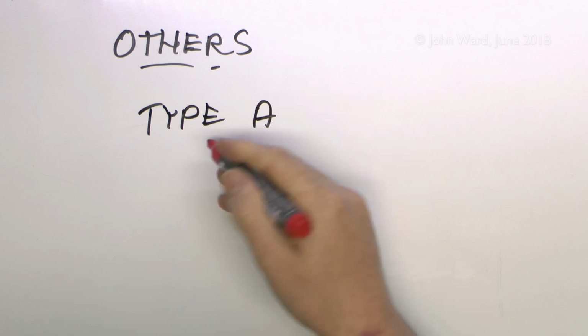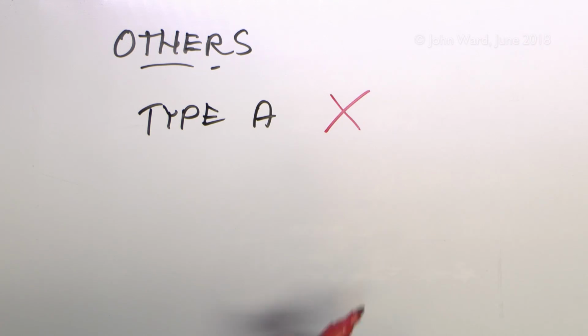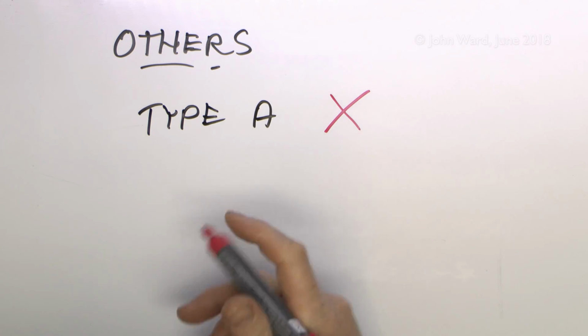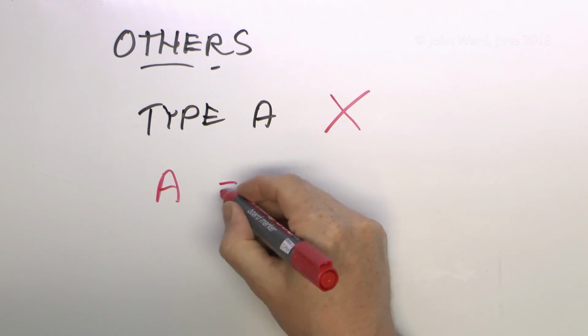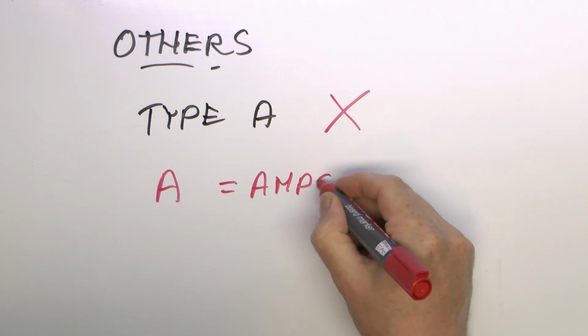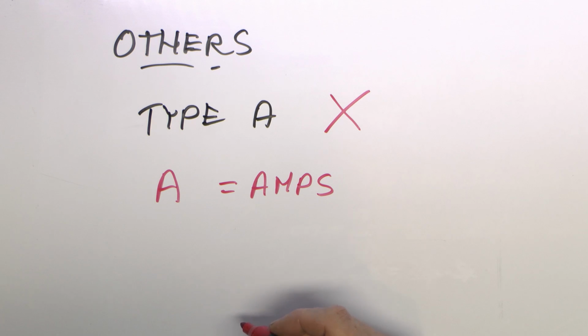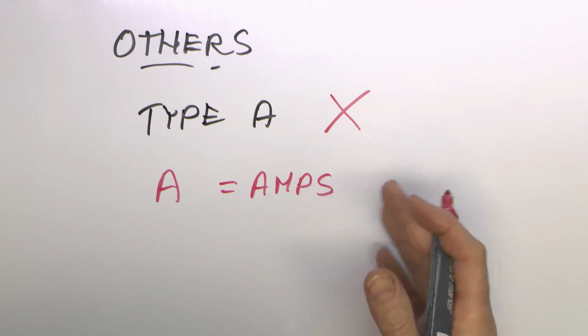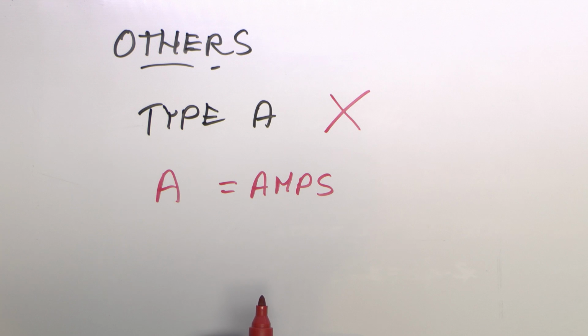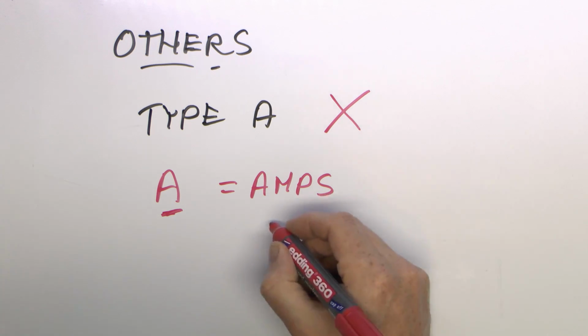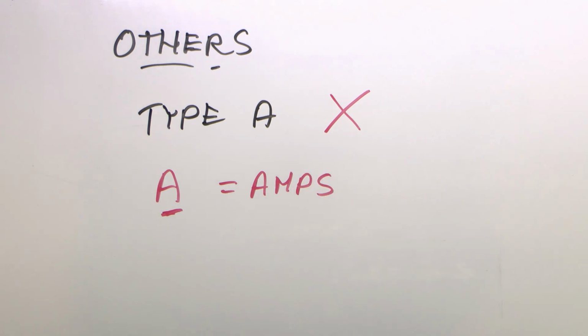And the final point, there is no Type A, despite that it might seem fairly obvious. The reason being, of course, is that if you put A on a device, then it's probably going to mean amps. So clearly that would be leading to a bit of confusion, hence why the numbering starts at B rather than A. So if you see A on a device, it does actually just mean amps, hence you're not going to see it on a circuit breaker marking the type. So no Type A, but B, C and D are available, and of course K and Z are also available as well.